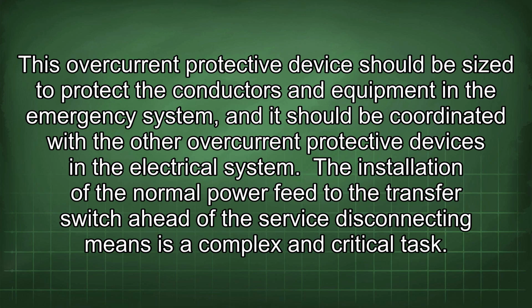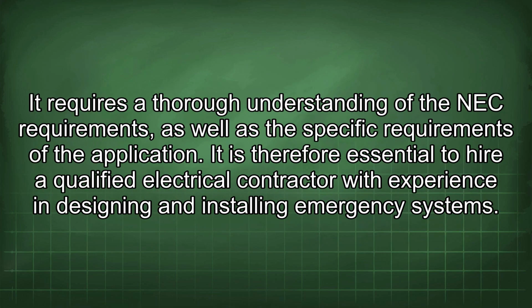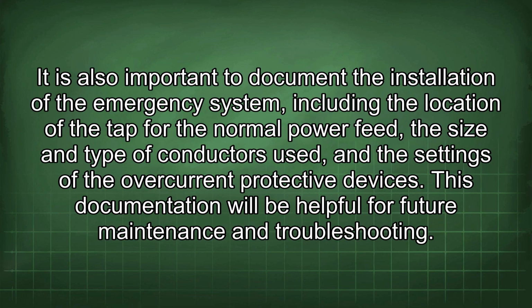The installation of the normal power feed to the transfer switch ahead of the service disconnecting means is a complex and critical task. It requires a thorough understanding of the NEC requirements as well as the specific requirements of the application. It is therefore essential to hire a qualified electrical contractor with experience in designing and installing emergency systems. It is also important to document the installation of the emergency system, including the location of the tap for the normal power feed, the size and type of conductors used, and the settings of the overcurrent protective devices. This documentation will be helpful for future maintenance and troubleshooting.